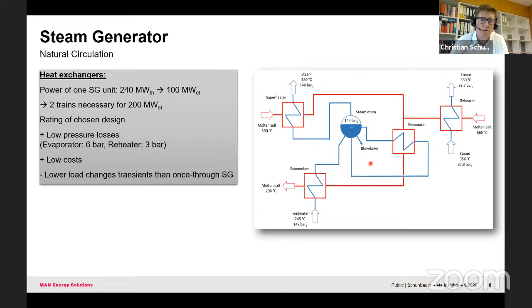The layout you see here now, I start again here with my mouse. The feed water comes into the economizer. We have 3 economizers in a row to preheat the water. Afterwards, the water goes into the steam drum. From the steam drum, it goes to the evaporator, which is placed here below. And from the steam drum, finally, the saturated steam goes to the superheater heat exchangers, which are fed in a row. And finally, the superheated steam goes to the turbine. For the reheater system, we also have 2 heat exchangers in a row. The heat exchangers are shell and tube heat exchangers, and as you can see here, we have one additional component. This is an electrical heater, which is used for startup and during standby to hold the system on temperature.